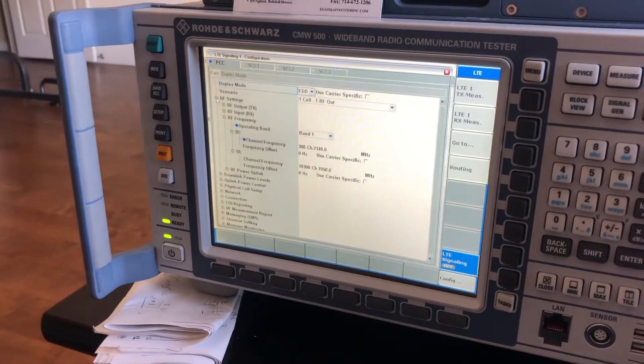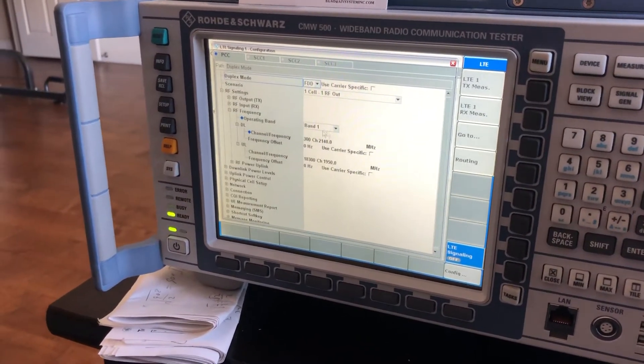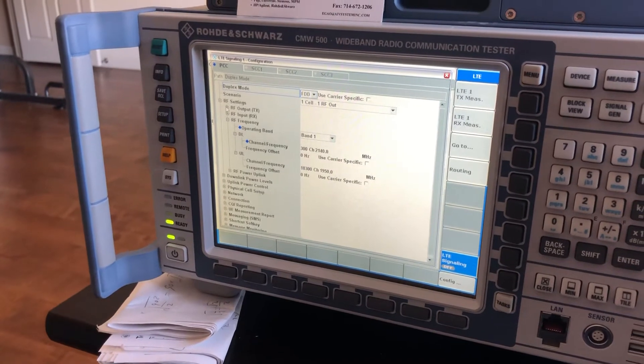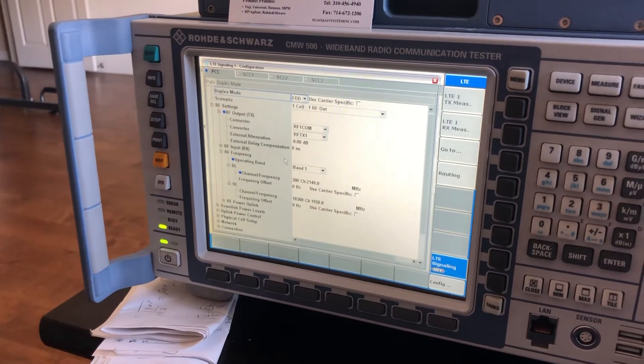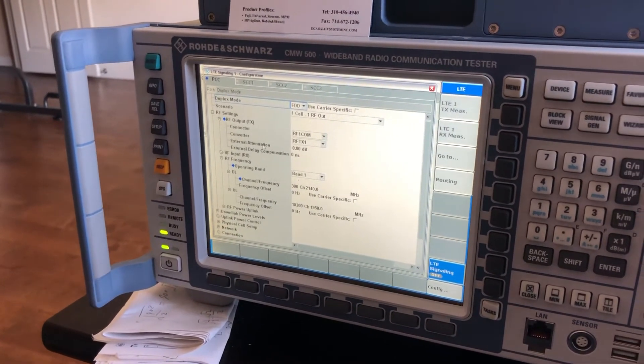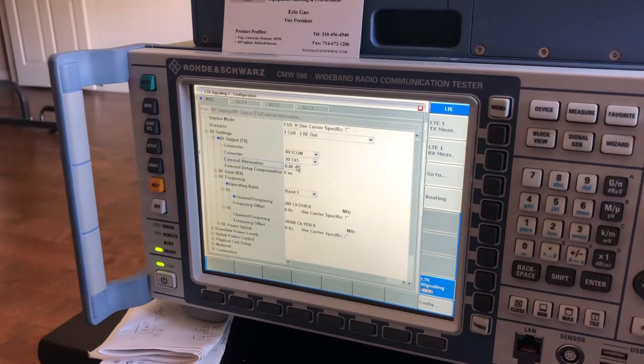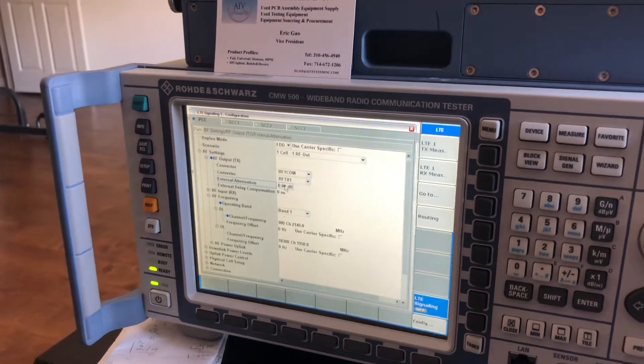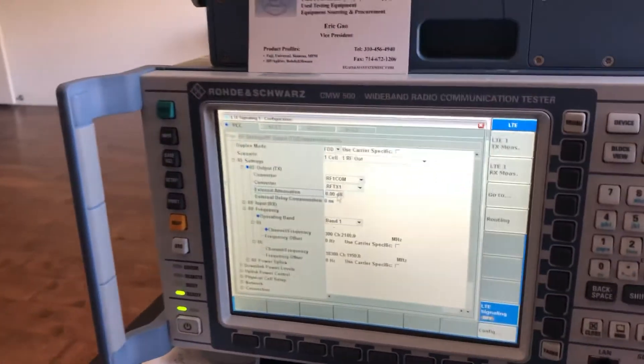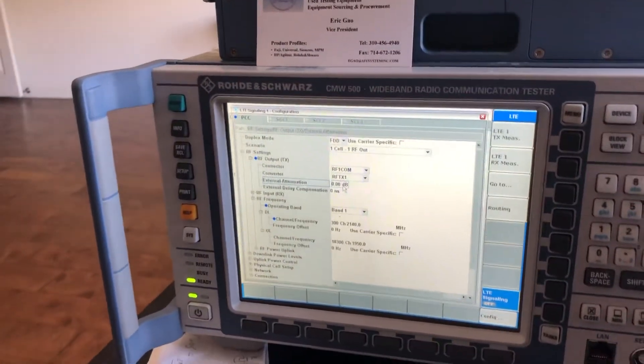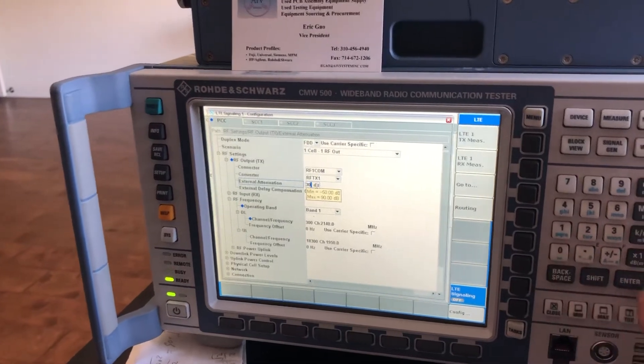First, set up the RF port. I'm using RF1, so you can see the mark on your front end. There is RF1 over there. Then you go to the RF setting. You need to make some compensation for your path loss.